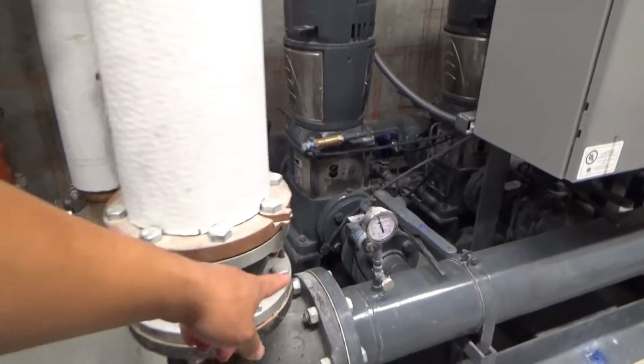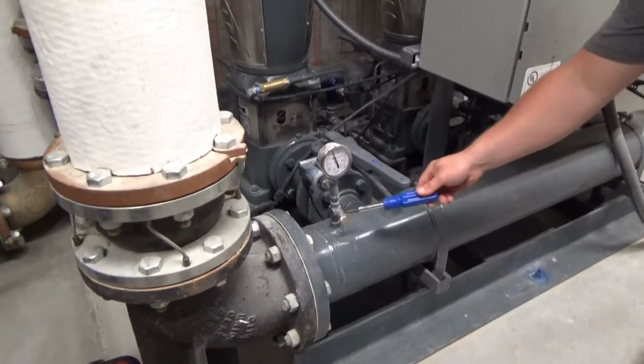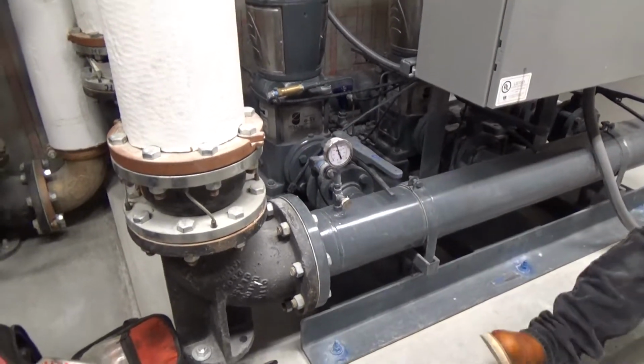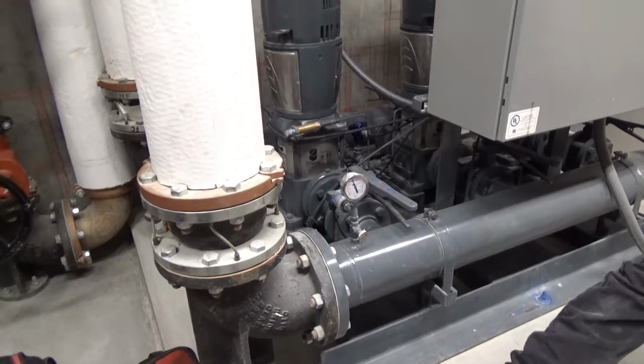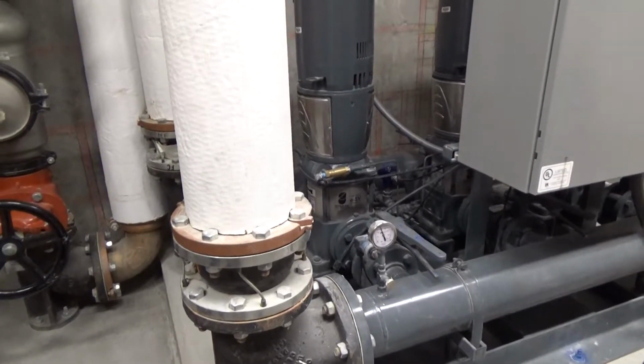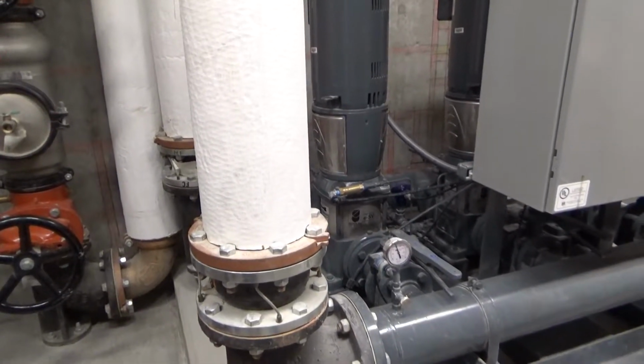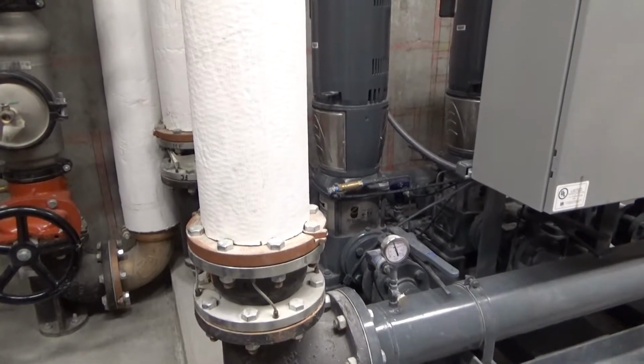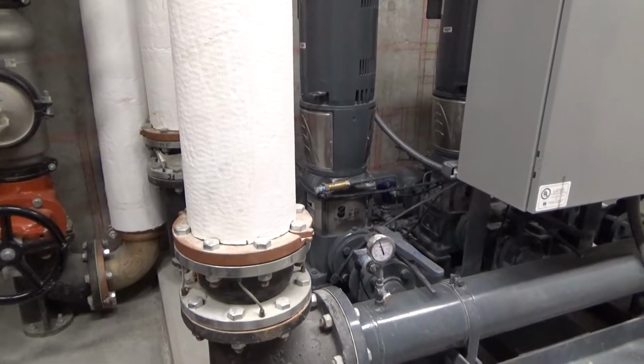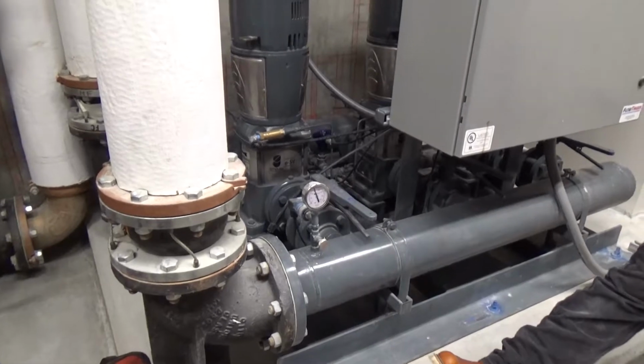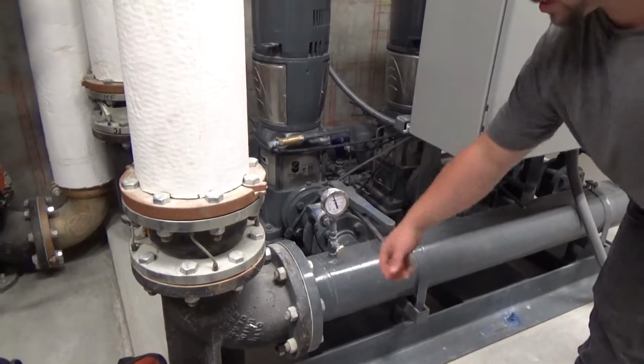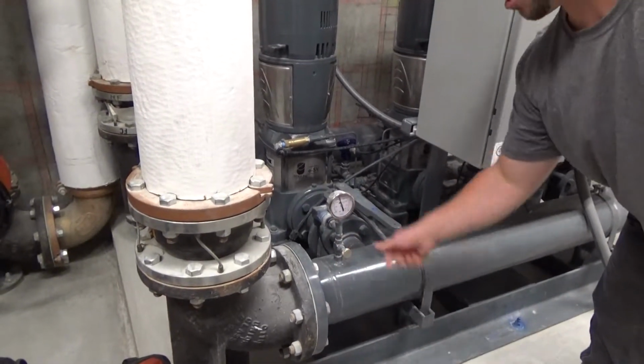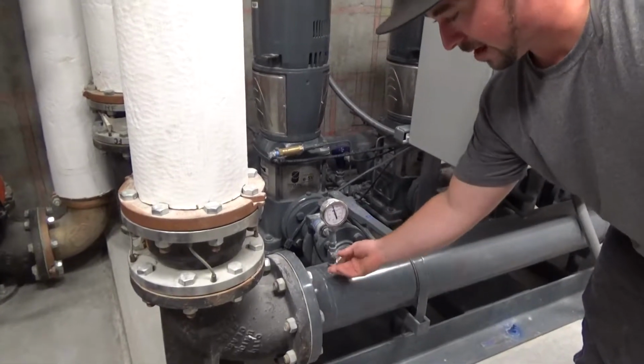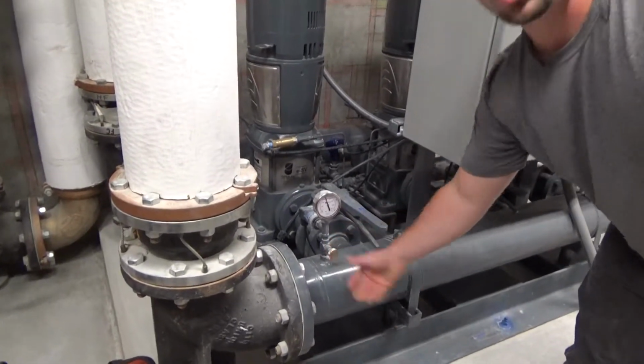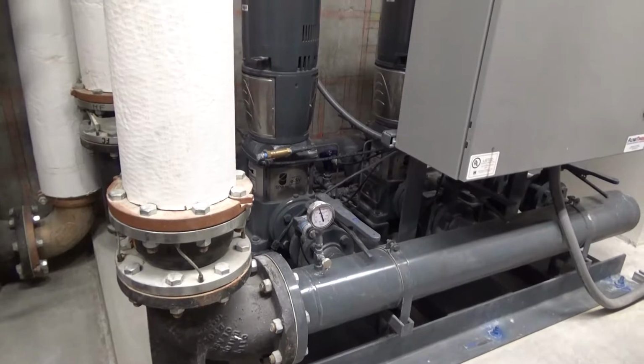What does that do? The one that's just turned? This bad boy? It's a valve. It's a ball valve, or a needle valve, actually. It's a very tiny little port, a little needle valve. It's good for gauges because you don't want a lot of flow going through there. It's just a tiny little pinhole, so say someone breaks this gauge, just close it, tighten it off, change your gauge, and open it back up. I always just open them all the way up and then do a quarter turn back. That's what I always check.